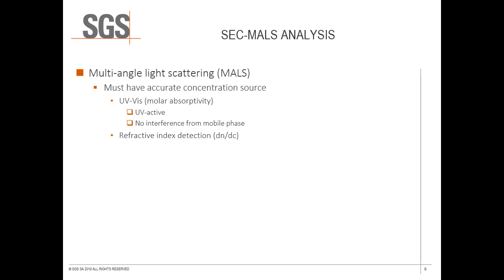The differential refractive index increment, dn/dc, is the change in refractive index of the solution when the solute concentration is changed. Good dn/dc values directly applicable to your sample are often difficult to find in the literature because dn/dc values are specific to the sample material, mobile phase composition, temperature, detector laser wavelength, and even the molar mass of polymer samples if the molecular end groups affect the refraction of light differently than the repeat units.